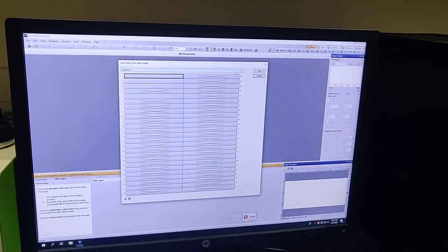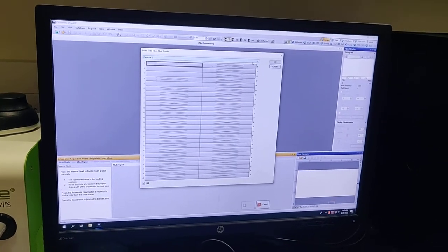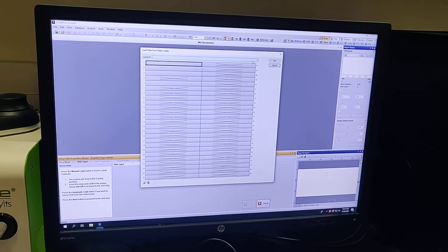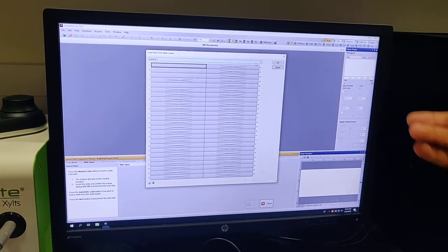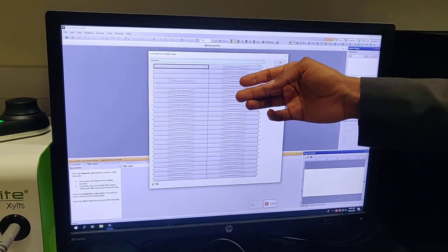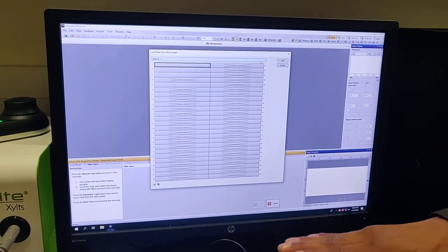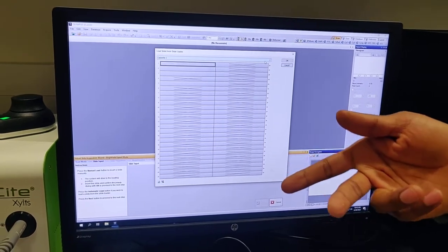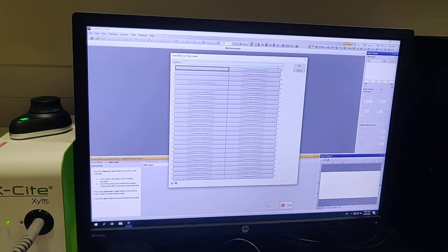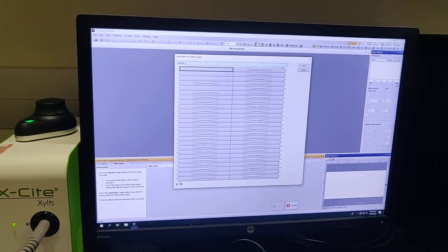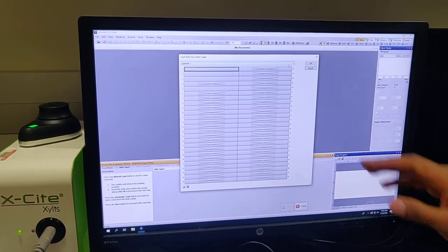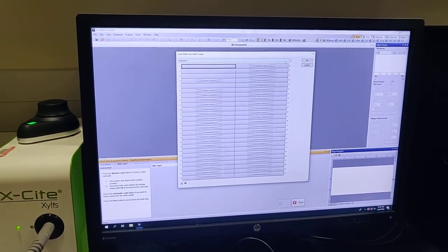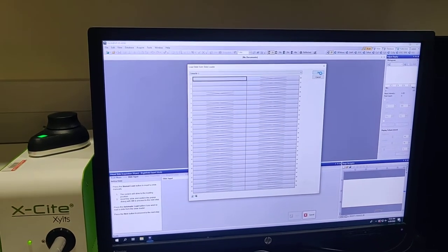If you are trying to do fluorescence imaging or even bright field imaging, the first slide should be the ideal slide, the best, because you will be using the same parameters ideally to image everything else. If you are having three samples, like one is control, another is super bright, another is super dim, I will image the brightest one first. Because if that can be imaged, anything lower than that can be imaged. It is very important that we image the best sample and the brightest one first and set the parameters accordingly.